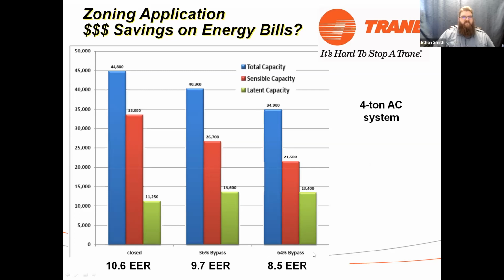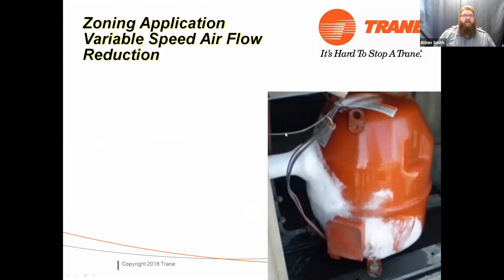Okay, so is that bypass saving me any money? Absolutely not. Okay, it's costing me money to run that bypass because I'm lowering the capacity of my equipment, but I'm pumping the same amount of electricity or possibly more into it. Okay. So one of the ways that we can actually apply zoning and make it save us money, and this is one of our excess air relief strategies that I like to use, is with the OEM zonings, a lot of times when they're integrated, you can actually reduce the airflow. Okay. Most air conditioners, believe it or not, will tolerate up to 30% reduction in airflow and still work.